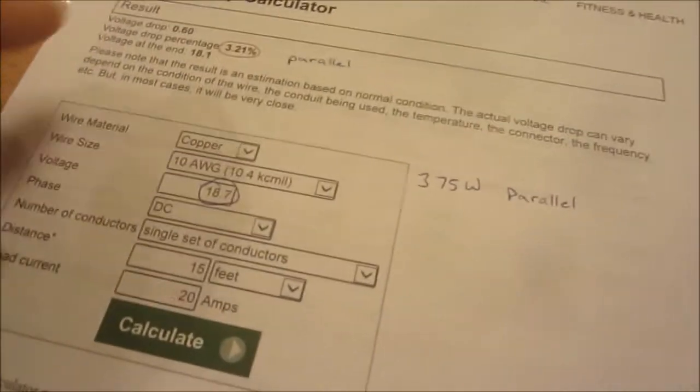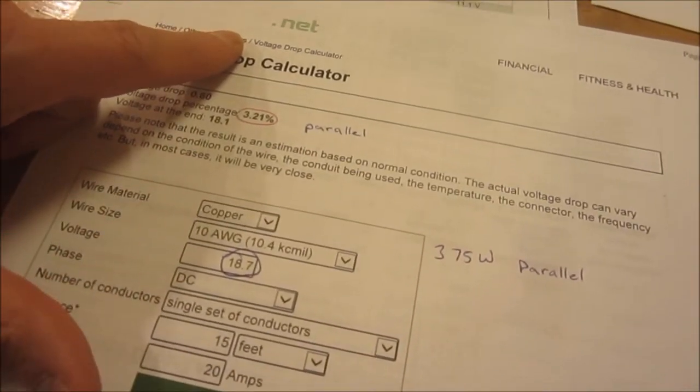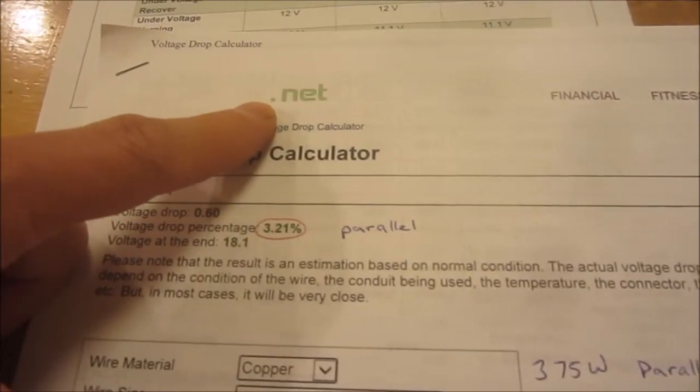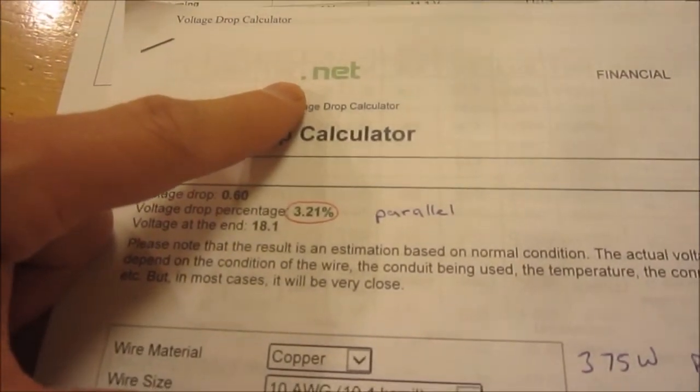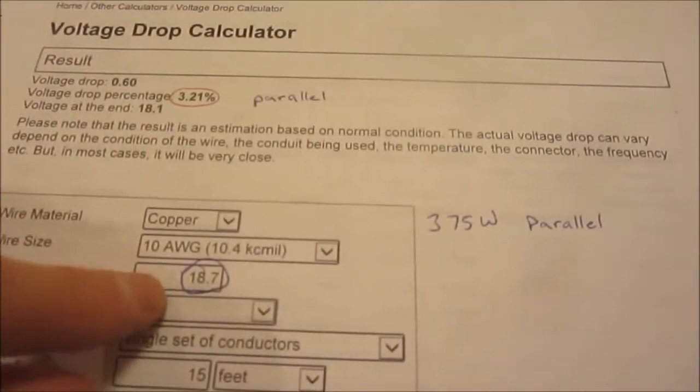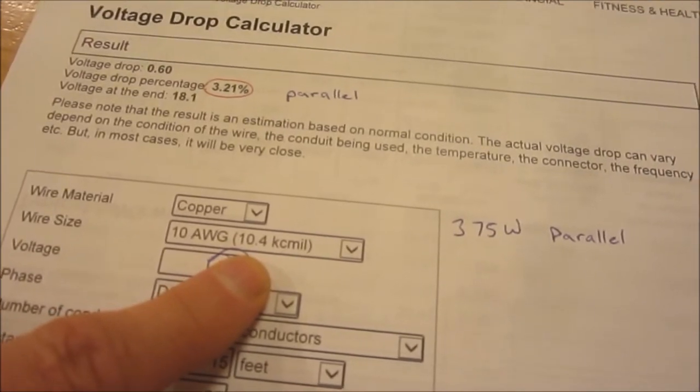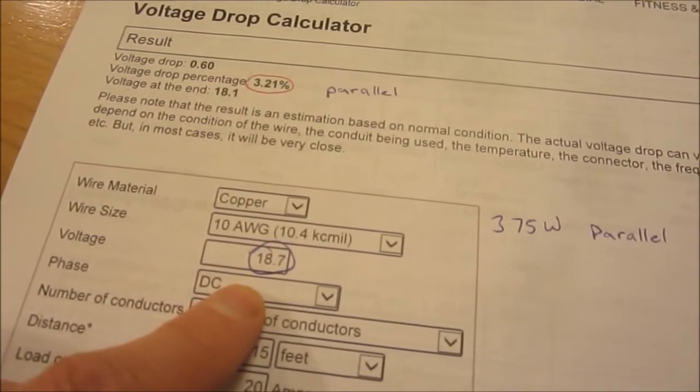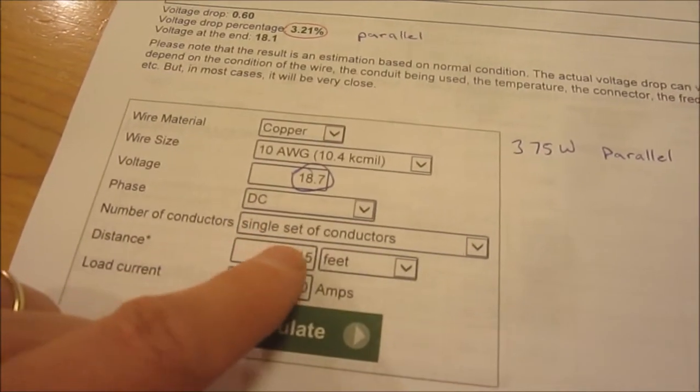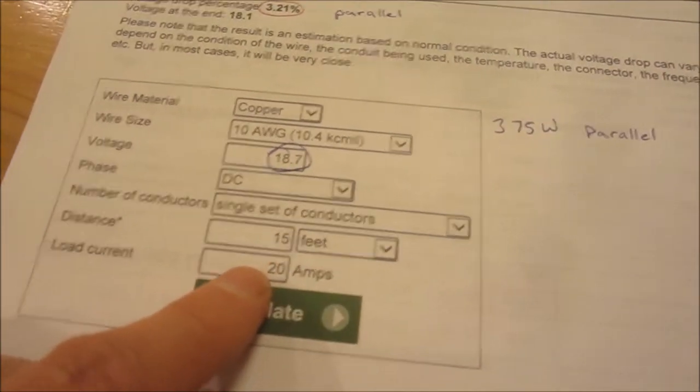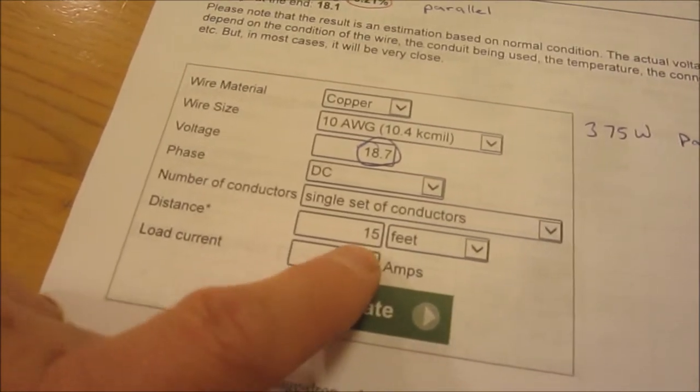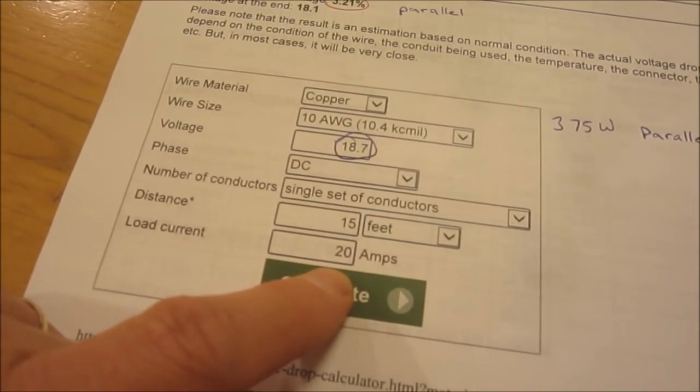And this is calculator.net. I'm going to include a link for that in a panel up above or on the top right about here. Click on that, it will also be in the description. On this I'm able to select my wire size, what my voltage is from the panel, DC wire single set of conductors, and the distance. So I selected my 15 feet and my 20 amps.